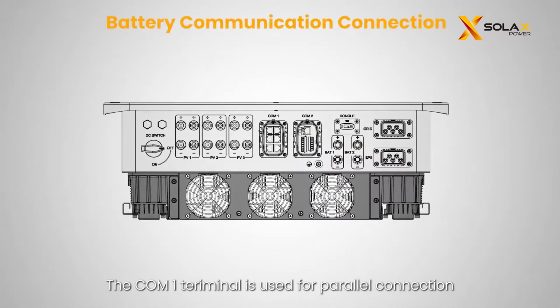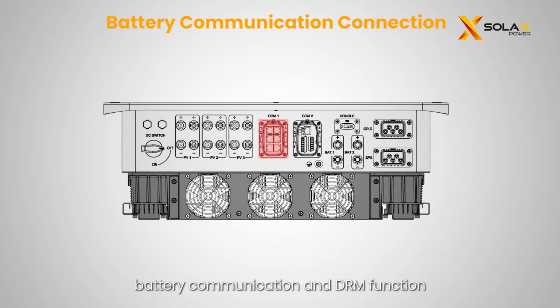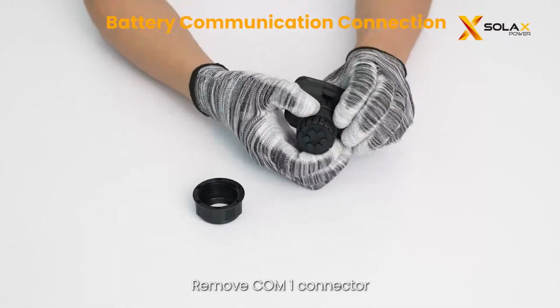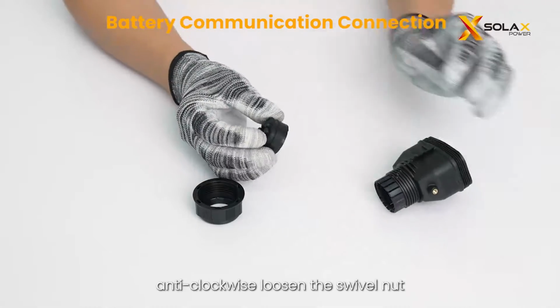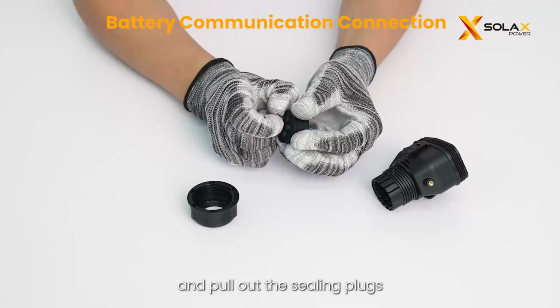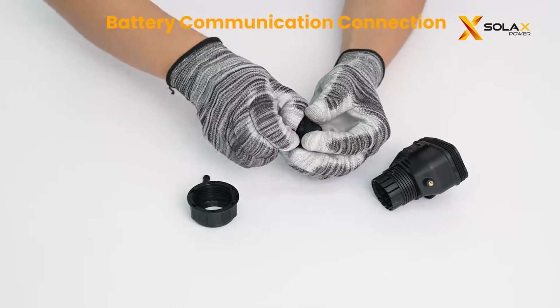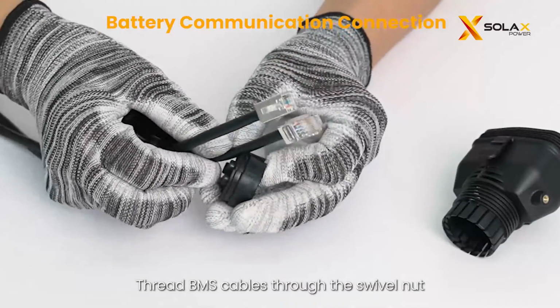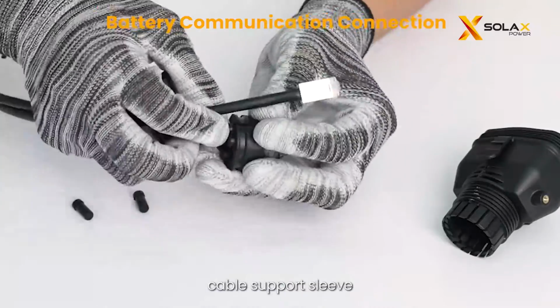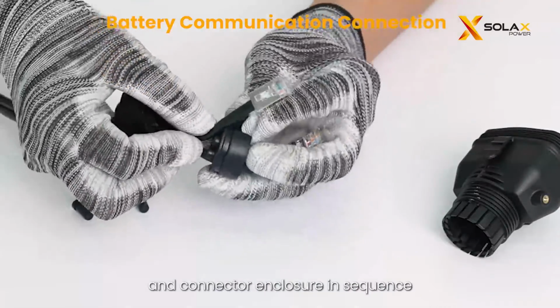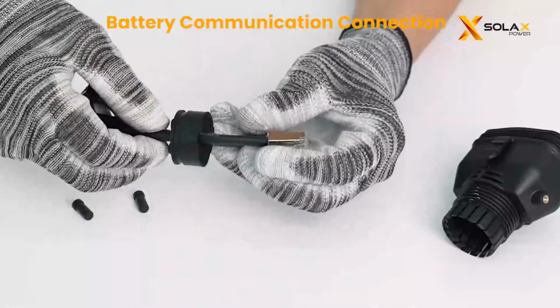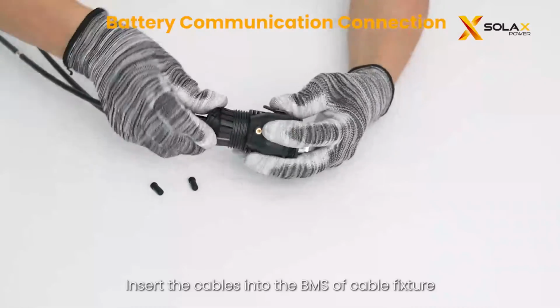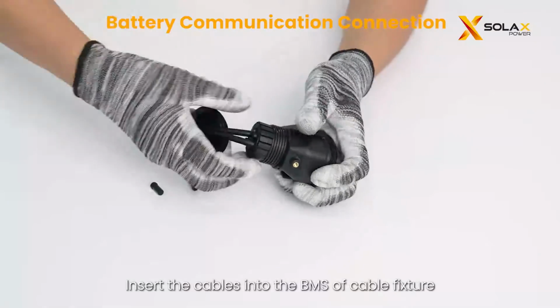The COM1 terminal is used for parallel connection, battery communication, and DRM function. Remove COM1 connector, anti-clockwise loosen the swivel nut and pull out the sealing plugs. Thread BMS cables through the swivel nut, cable support sleeve, and connector enclosure in sequence. Insert the cables into the BMS of cable fixture.